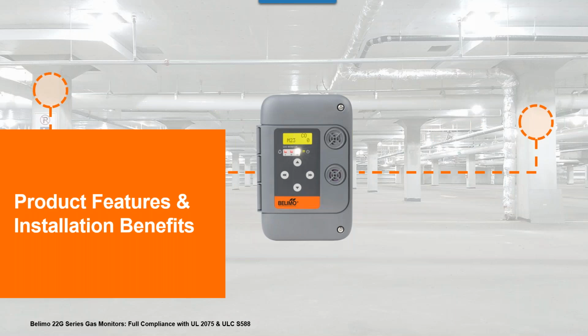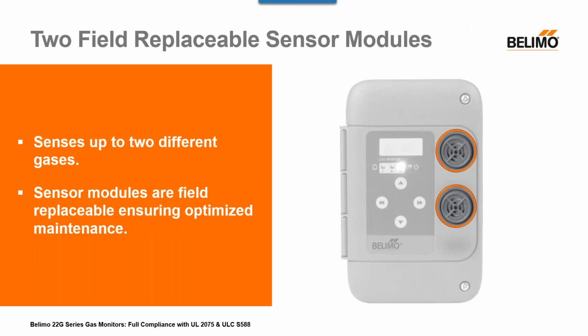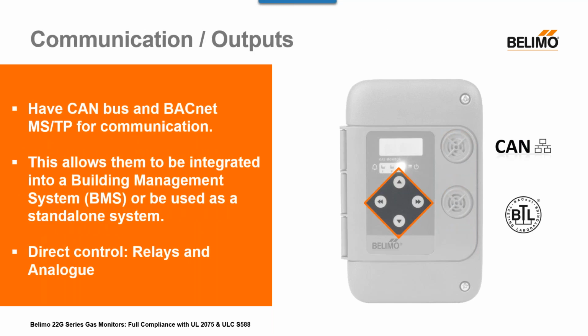Let's take a look at a very high-level summary of the product features and installation benefits and how we are unique to the competition. Each monitor can detect up to 2 different gases in one single monitor, thus reducing hardware. The sensor modules are plug-and-play modular sensors, factory calibrated and also field replaceable if required. Belimo gas monitors offer an intelligent peer-to-peer communication protocol that provides users the flexibility to configure and install a complete ventilation control system with only one monitor or multiple monitors operating in several ventilation zones. This allows facility managers to achieve efficient ventilation control while maintaining compatibility with other building systems.